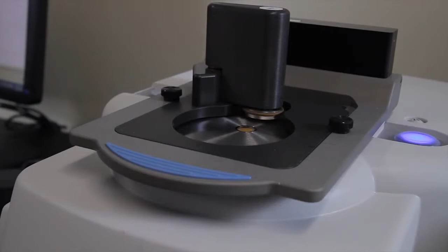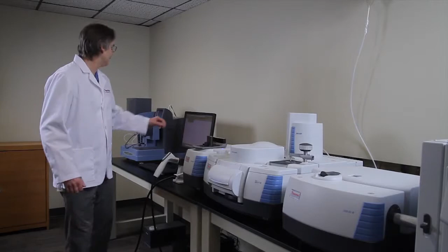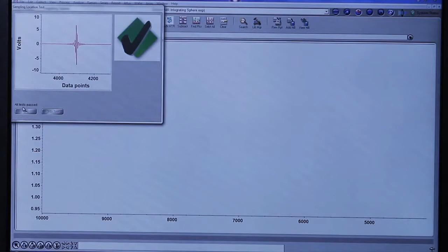First of all, we'll look at the integrating sphere. And one of the things I want to emphasize with the iS50 is that collecting spectra is as easy as just pushing a button. So I'm going to push the blue button here. The spectrometer will go through its paces where it swaps around different light sources and beam splitters. Eventually, it'll be ready. We'll see on the screen that the instrument is checking itself, making sure it all works out properly. And once everything works fine, we get a green check mark. Right now, the instrument is ready for the analysis.